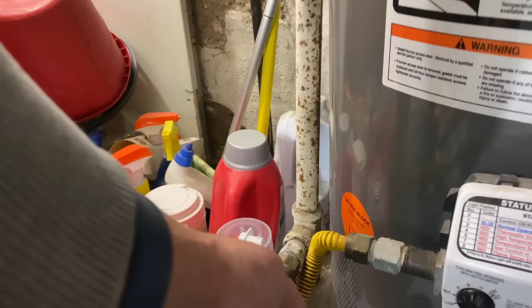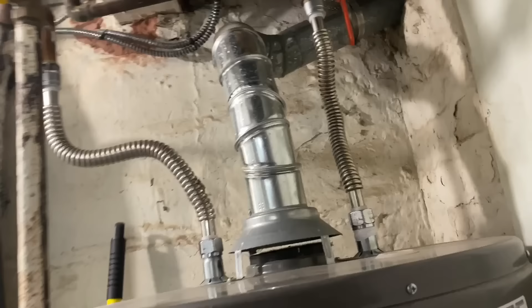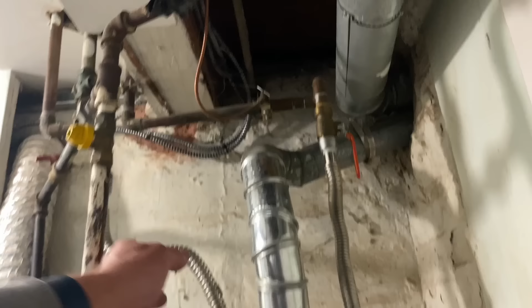Number two, this is wrong, and the flex on here. But most importantly, this exhaust pipe — I get it, the last one had a 3-inch pipe here, right, this is 4-inch, by the way. The last one had it, but that doesn't make it right. Just because you took out something and put it back the same way it was doesn't mean it's right. Here, my biggest concern with this, over everything — forget about the gas flex on the gas, forget about the flexible water lines, because the worst thing that could happen is this will break and it'll flood out the basement.